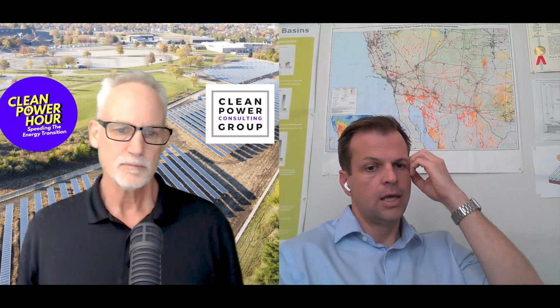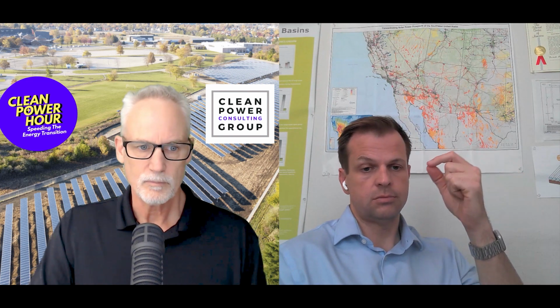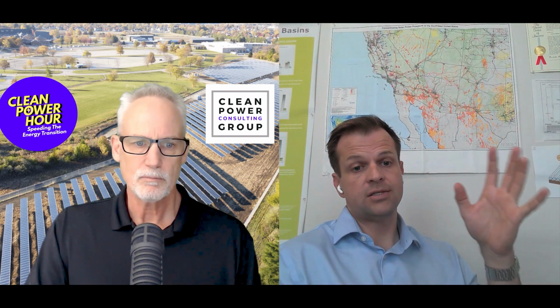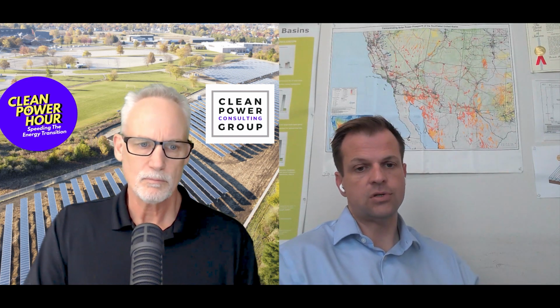For geological thermal energy storage, GTES, we actually benefit from six decades of thermal enhanced oil recovery that the oil industry has already done. The first steam floods, as they're called, started around 1961 in Central California and have been operating ever since. So it's not really a science project. They know very well the thermal round trip efficiency of doing this. They've studied it, put in monitoring wells, measured temperatures at production and injection wells. You're talking about 75 to 90% thermal round trip efficiency over 6 to 12 months, really high efficiencies over long periods of time.